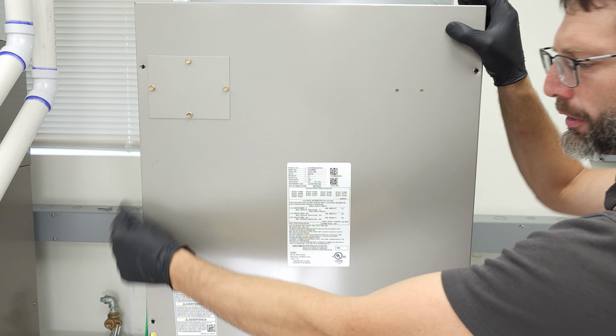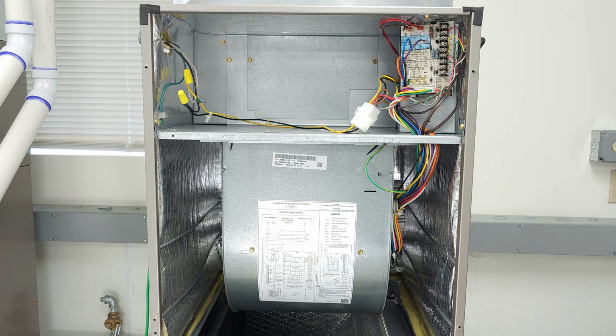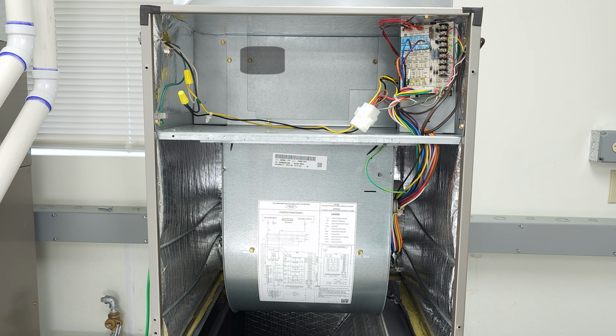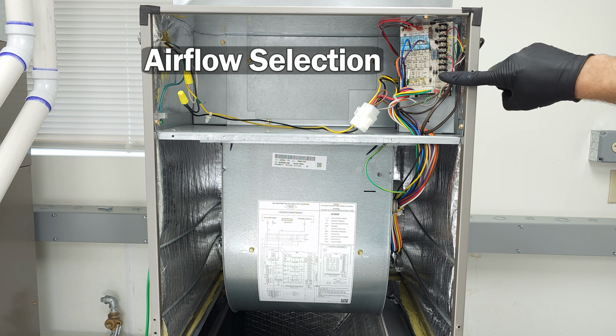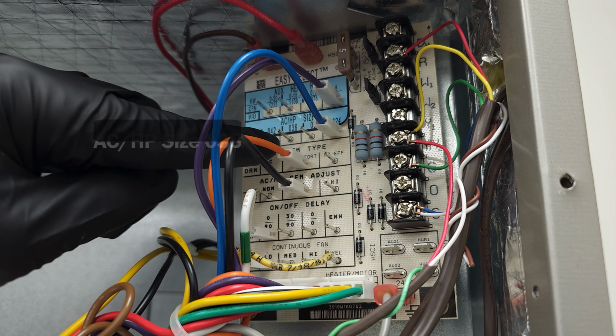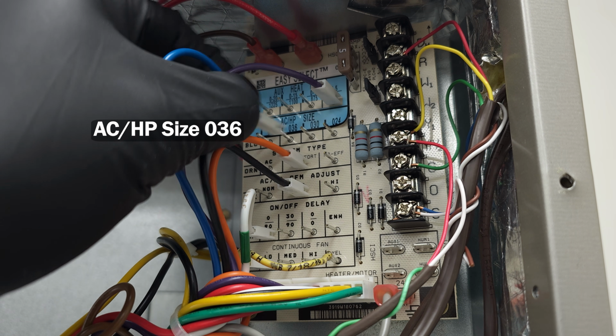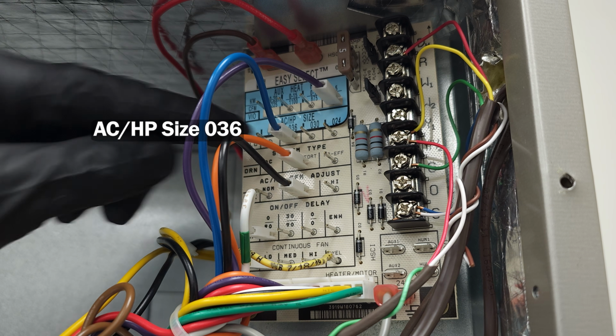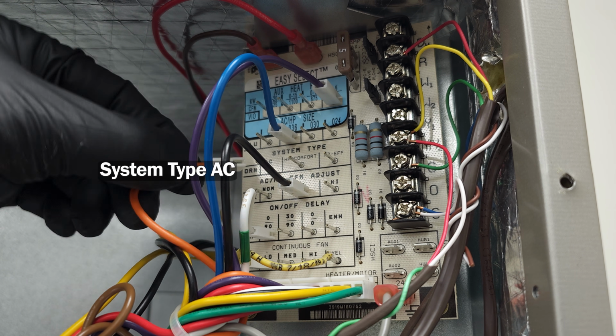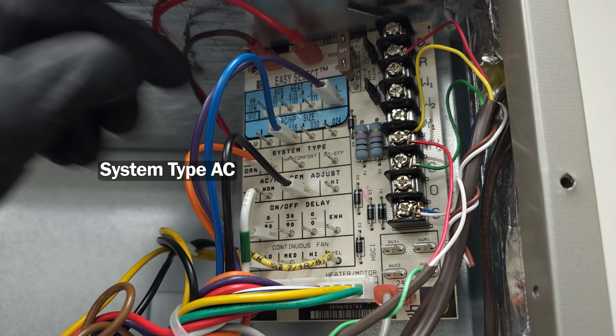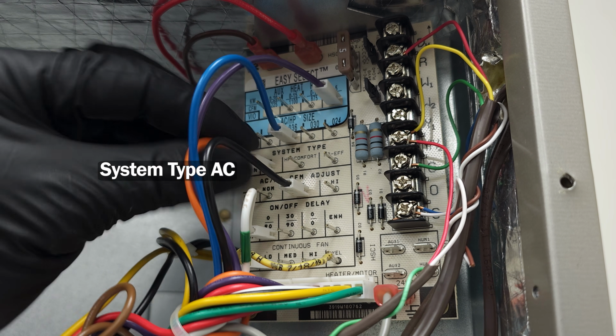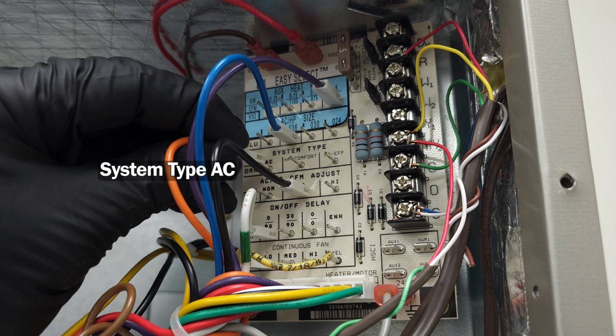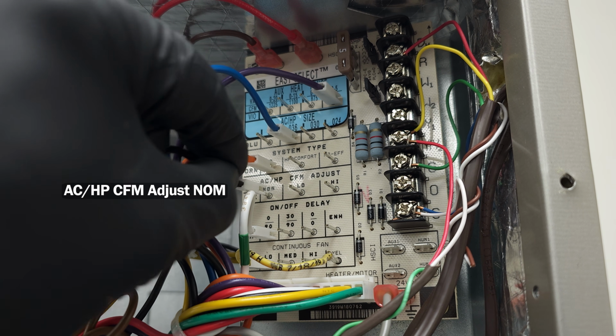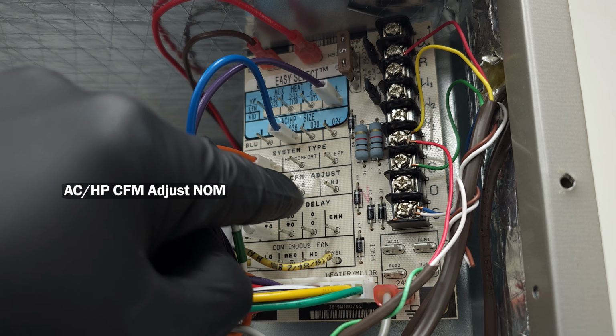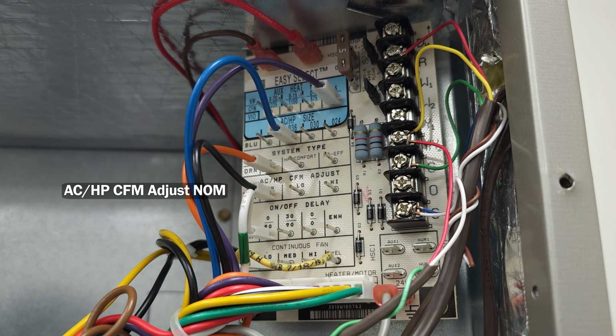Want to make sure to turn the power off to your unit. We're going to remove our cover. And then we have our airflow selection right here. So as you can see right here, the size, we are actually at a 36. So we're going to move this from the 24 to the 36. System type, this is AC, so we're just going to move this over to AC right there. So you can see that. I don't know if you can see that or not. AC. Then we're going to move the CFM adjust to nominal instead of low or normal.